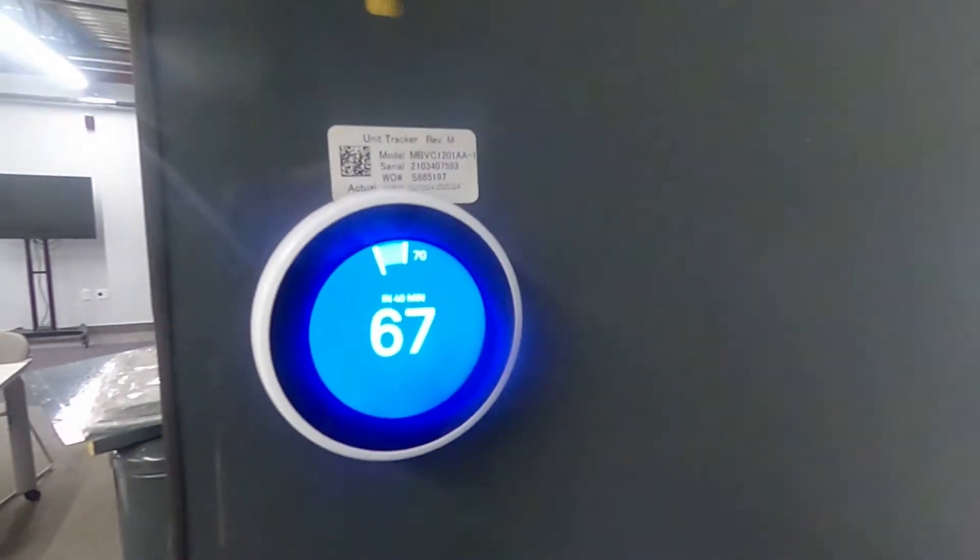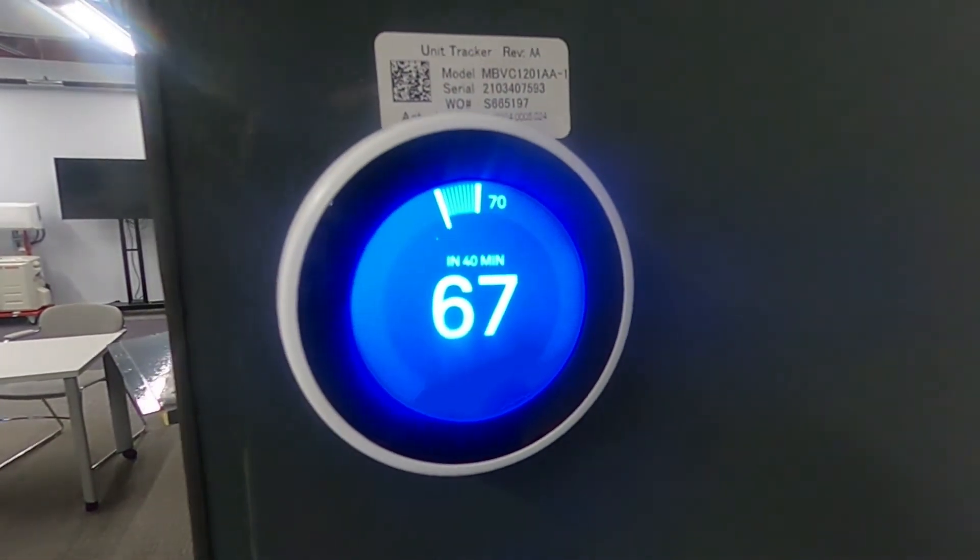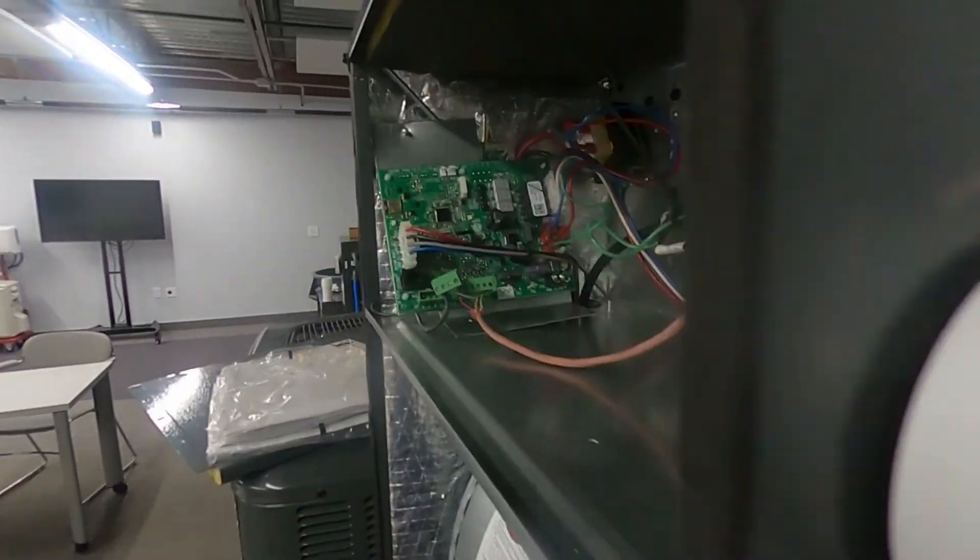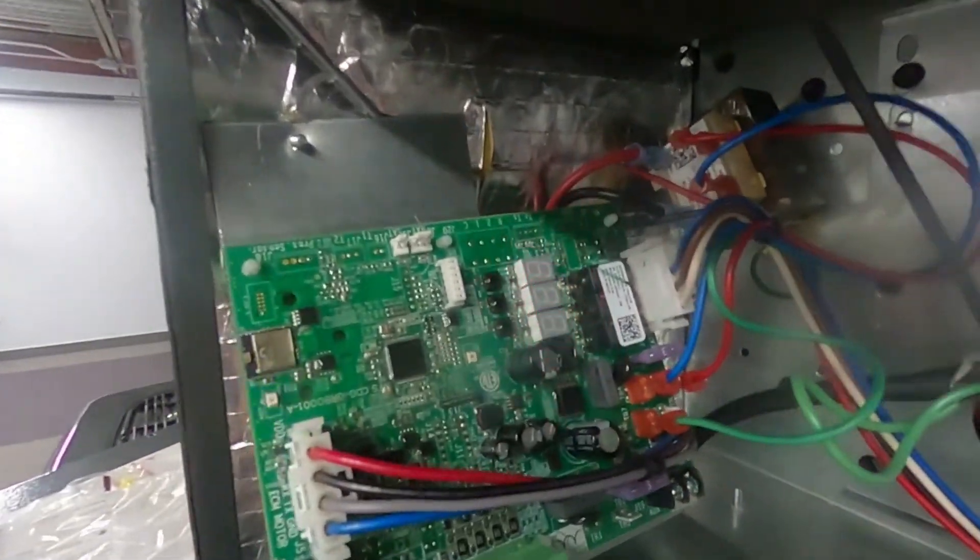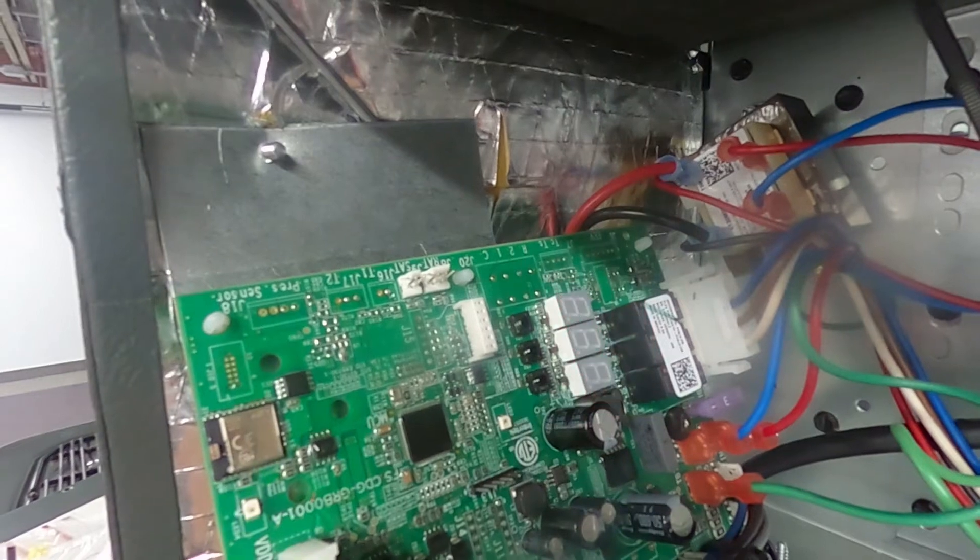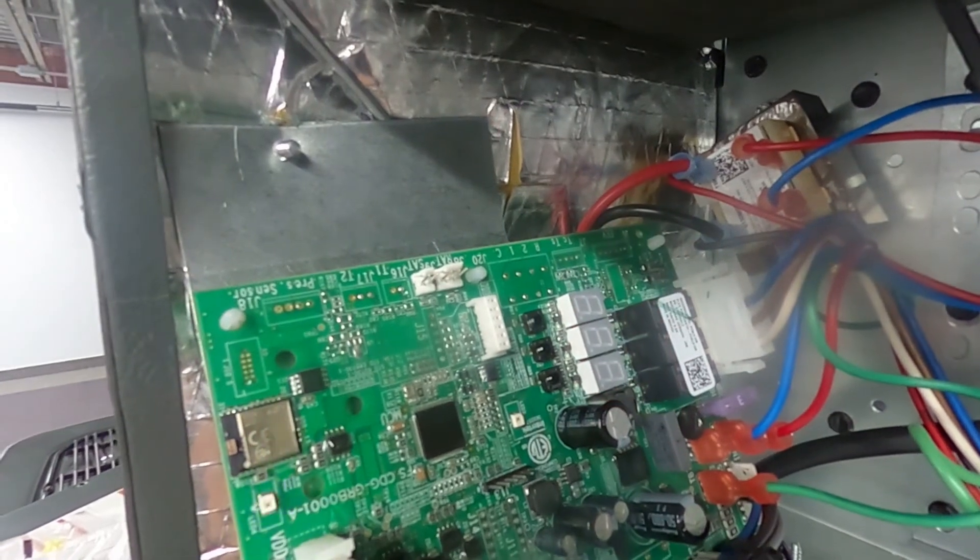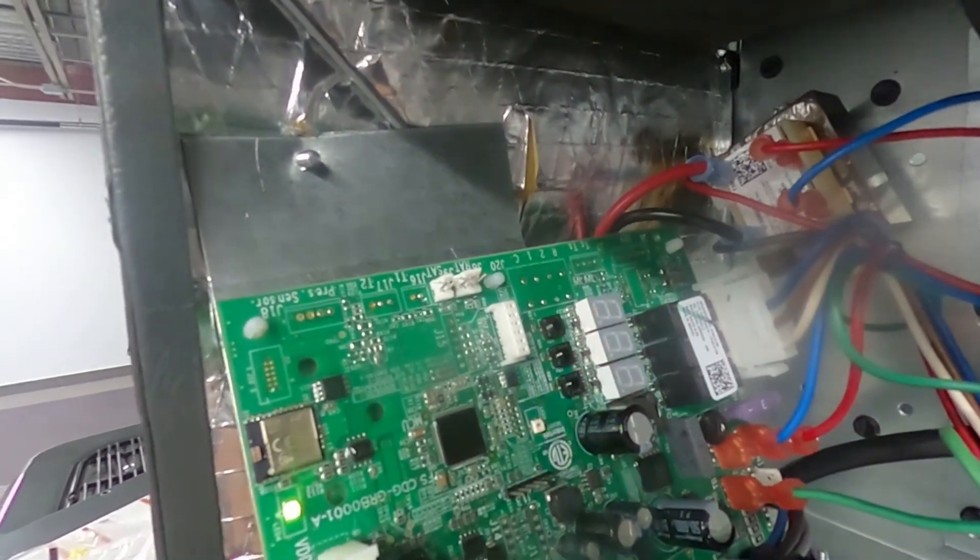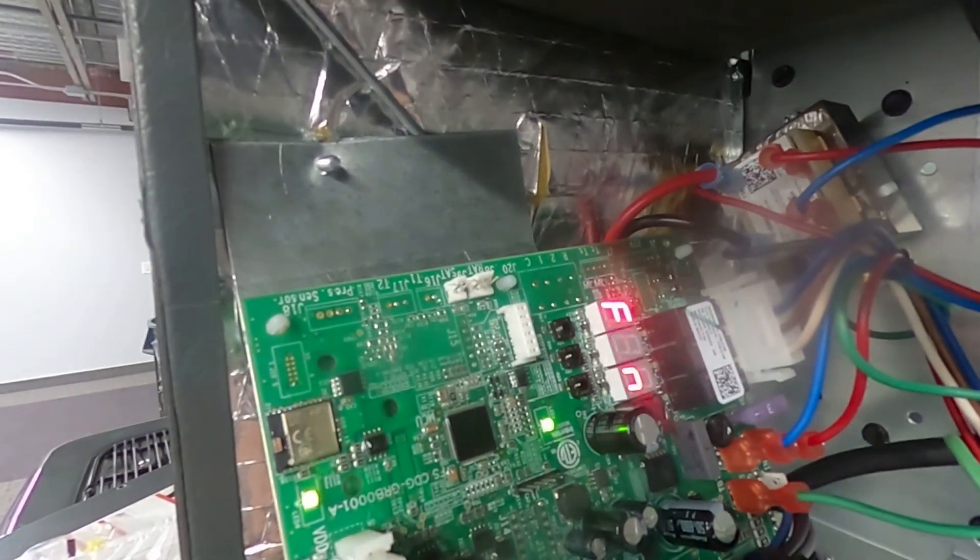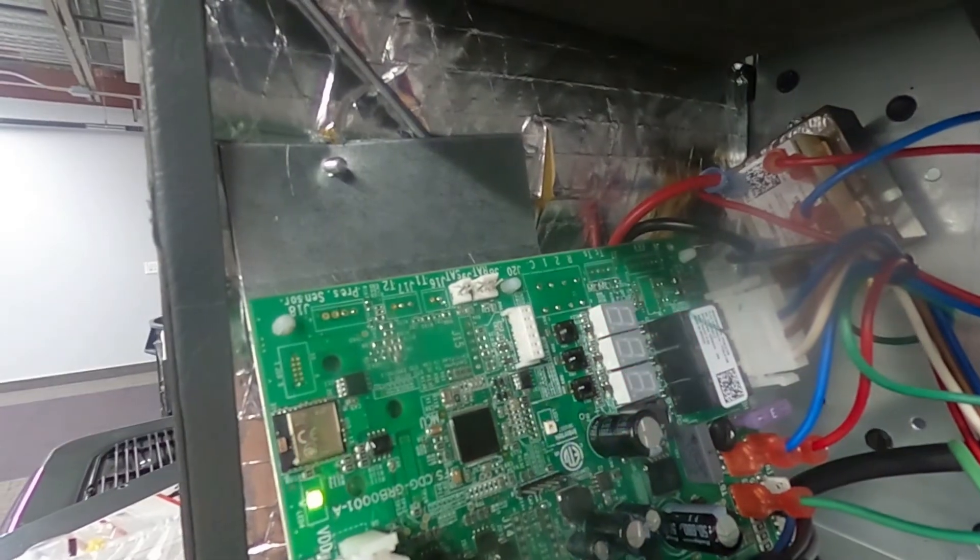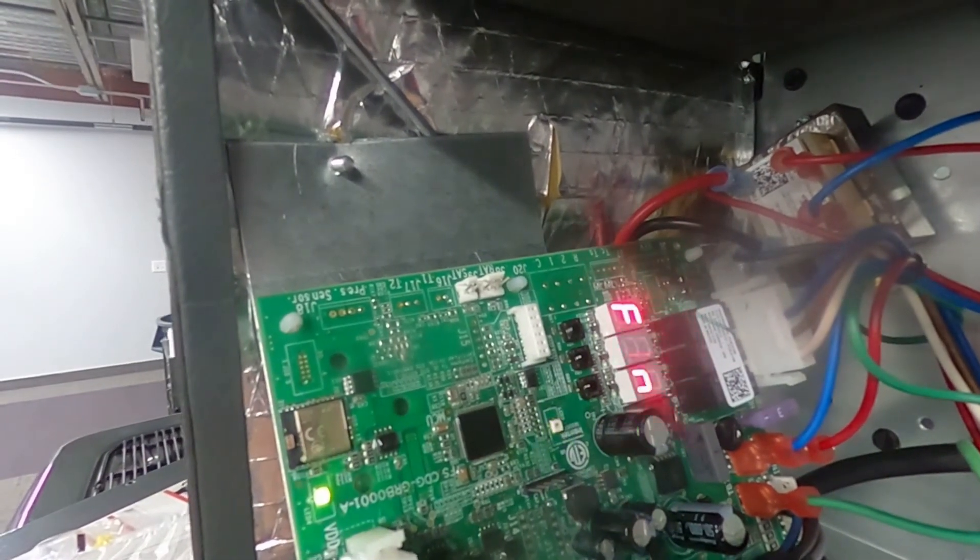All right, this is just one of the lab units we're taking a look at here. You'll see I'm calling for cool on the thermostat. You'll see the communicating equipment in the bottom left disconnected because I'm going to wire it legacy. But you'll see we're only seeing the fan call.